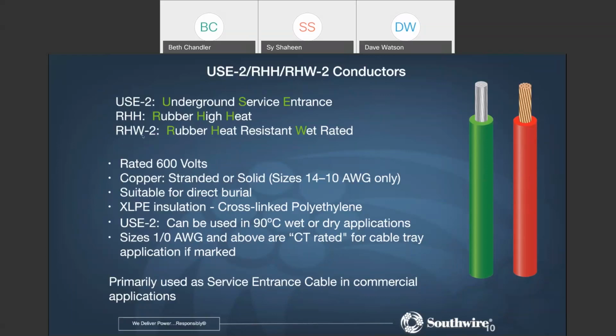At this time, this product is rated 600 volts, maybe rated 1,000 volts a bit later, but it is made of the same type of material, meaning it's a cross-linked polyethylene, similar to the XHHW type of conductors. Now, the RHH and RHW-2 designations are recognized within the NEC for building wire use, meaning that this product, like the XHHW and THHN conductors, can be used indoors.